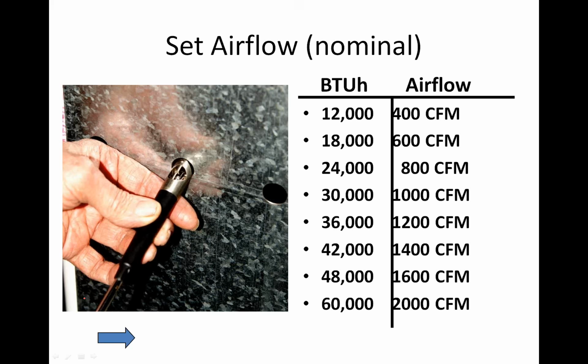So it's sort of a way of working the system to get higher SEER out of the equipment, because we can make the compressor work less when we have a higher suction pressure. But on the other hand, we don't dehumidify as well. So what they're doing is they slow that fan down to 350 CFM per ton to get the humidity removal, so it actually doesn't operate at its optimal efficiency all the time like you'd anticipate it would.